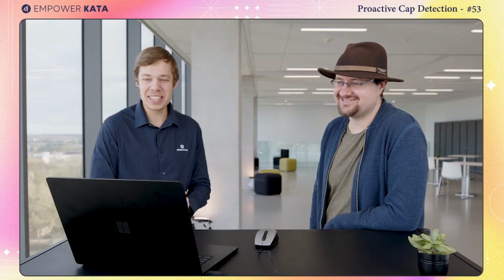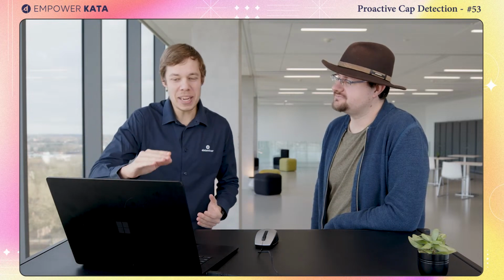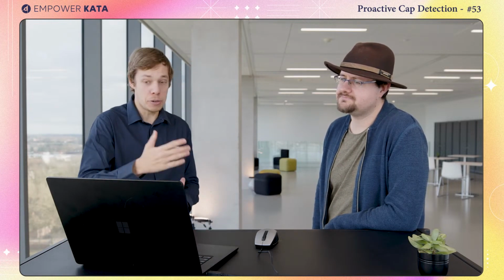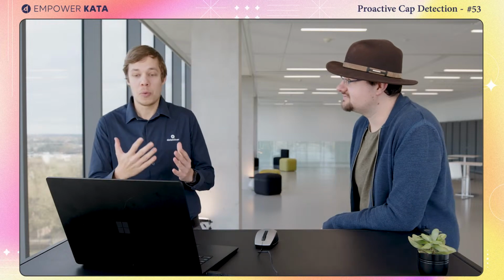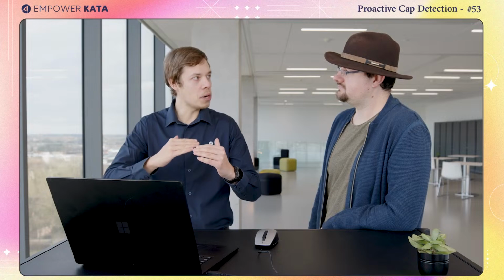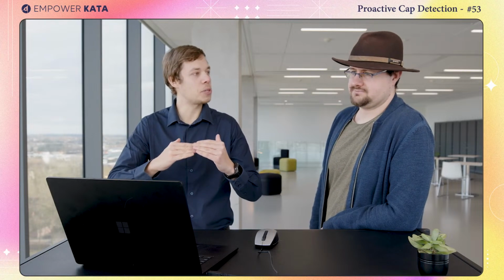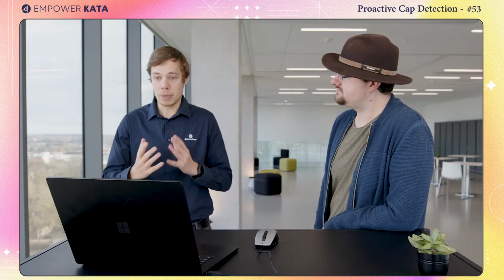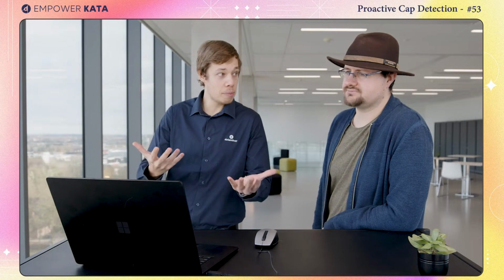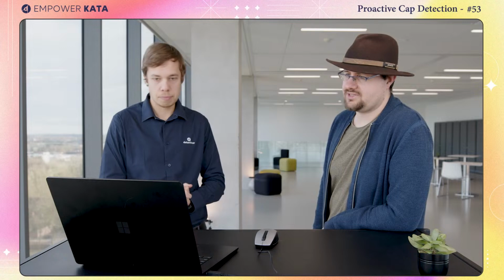What I wanted to say still is, what is now the big advantage of doing it this way? Like you suggested, put a critical low threshold on -9. Then we also have an alarm, right? What is the advantage of doing it this way is that you can put your alarm thresholds lower, and that way avoid false positive alarms. But you still get an early warning when a parameter is trending towards that threshold. So it's a way of still getting notified, but avoiding false positives.